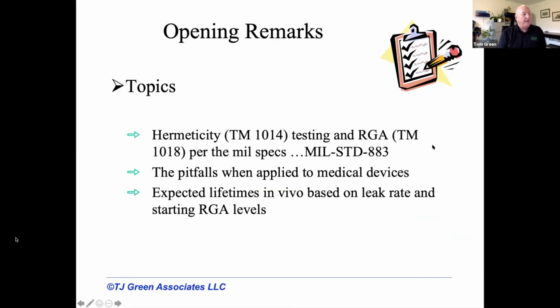So, all right, today I'm going to briefly go over some of the test methods in MIL-STD-883 regarding hermeticity. The big one is test method 1014, which spells out all the procedures and methods for determining whether or not you've got a good hermetic seal. That test method is closely related to another one, test method 1018, for residual gas analysis. Now, many years ago, the medical device community adopted these standards, and there are some things to be aware of when you try to apply these test methods to a medical implant.